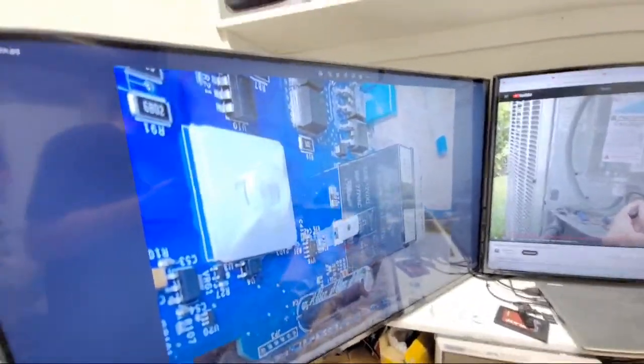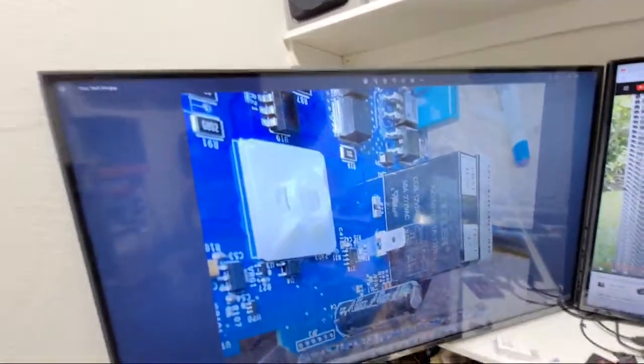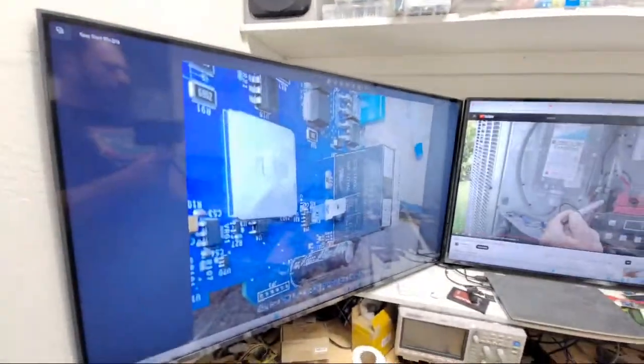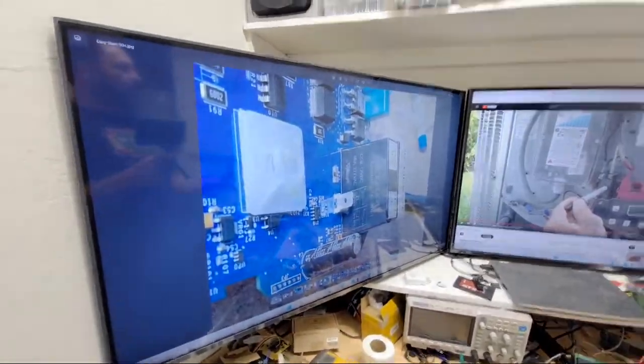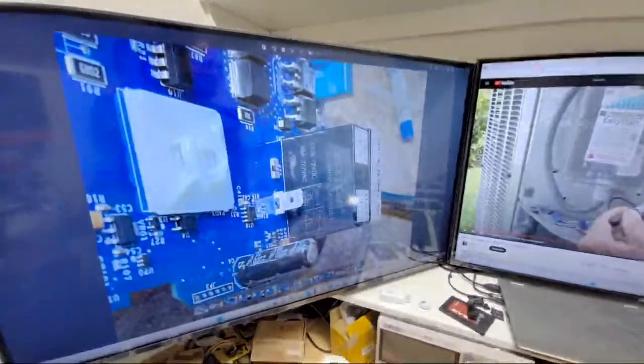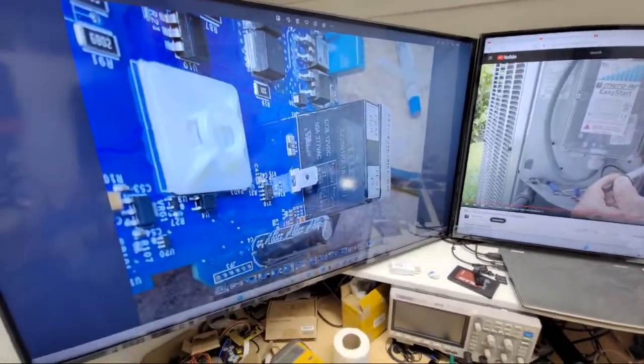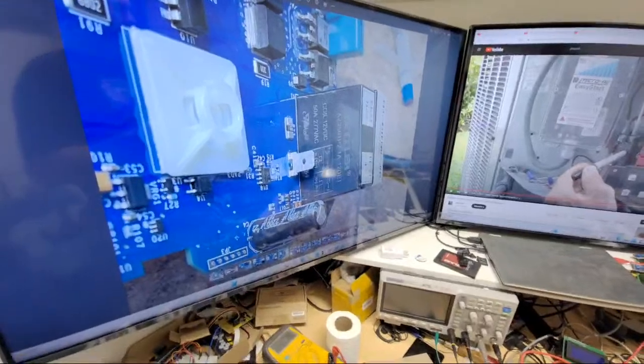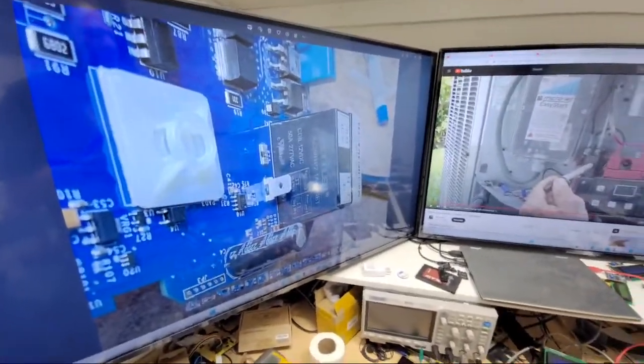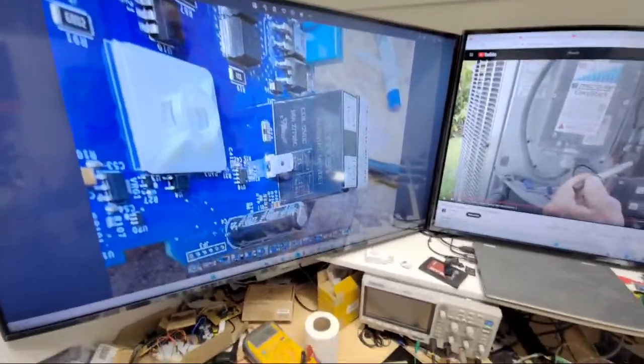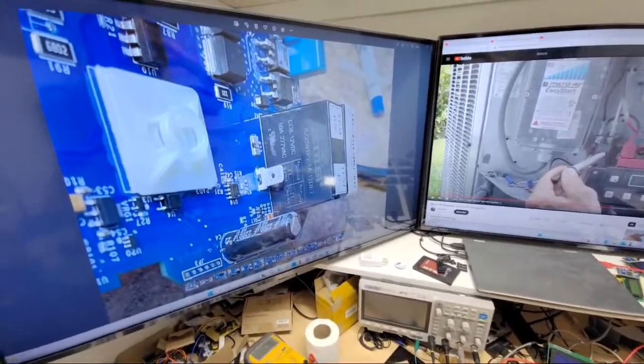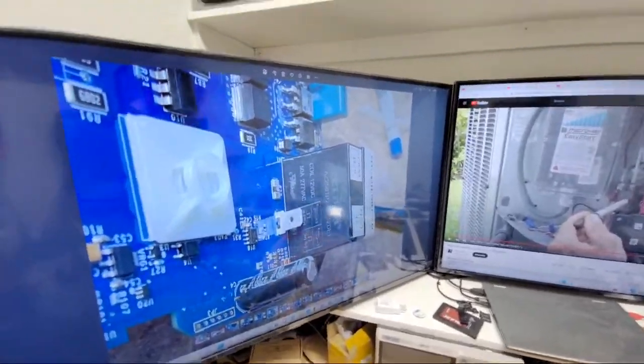It's just a delay and some fine control on the start capacitor, instead of using a fixed timer on a relay or a potential relay, or like what Super Boost used to do, which was destructive—using a full one-second holding circuit no matter what, even though the compressor was already started. That was not good for compressors.